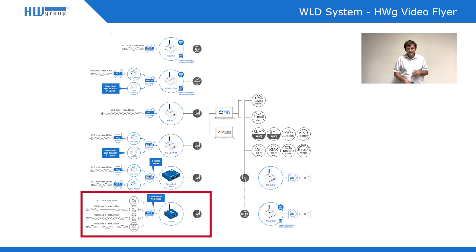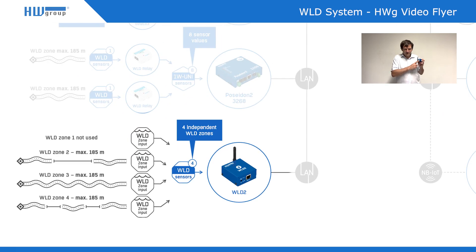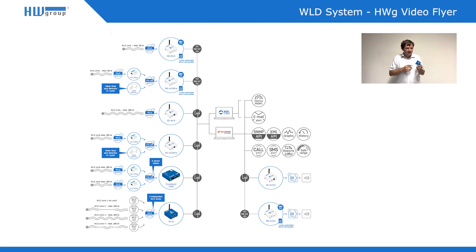The second option is that up to four different zones can be connected to this green terminal block — four connectors, four different zones. Each zone is 185 meters and can be connected to the WLD2. This product can send you email alerts directly, SNMP traps, or alert you via SMS or call through the GSM gateway. The portal for this device is only optional, and that's a benefit.